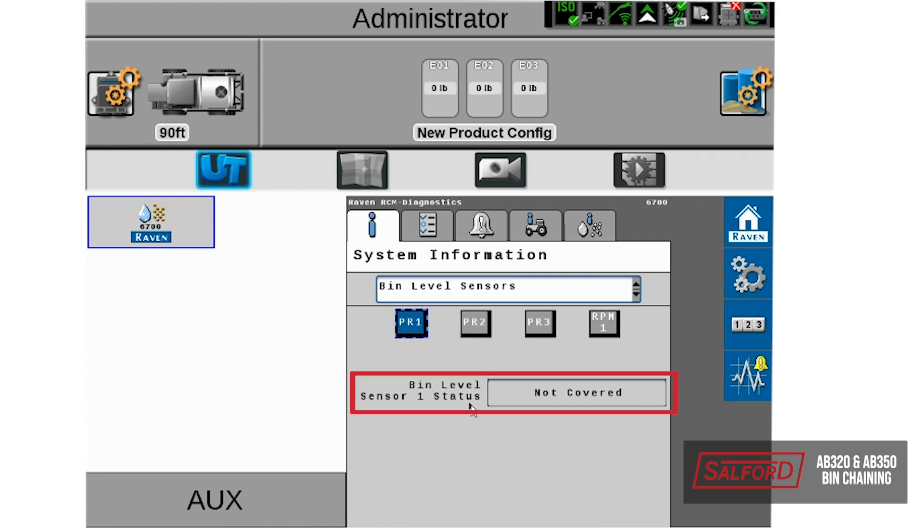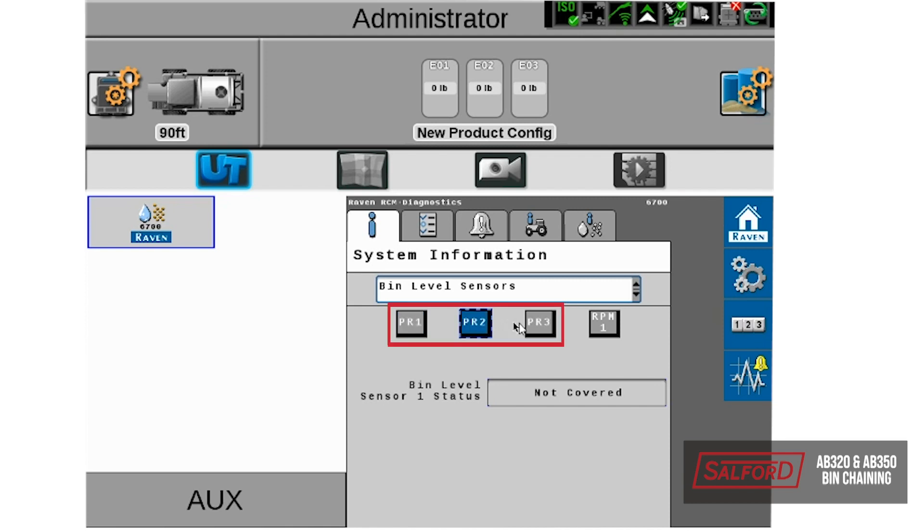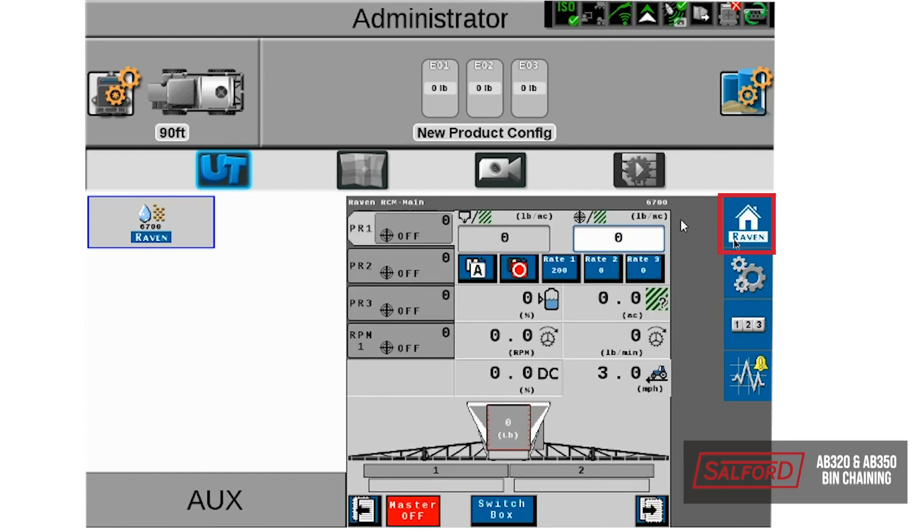On this page, we can see the status of each bin level sensor. Ensure that it reflects the status of the bin, so if you have product in the hopper and they are full, they are reading covered. If they are empty, they are reading not covered. Tap through each bin level sensor to ensure they are reading properly. Once you have confirmed they are reading properly, we will go to start a job.